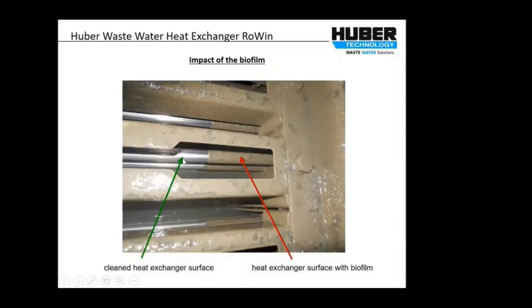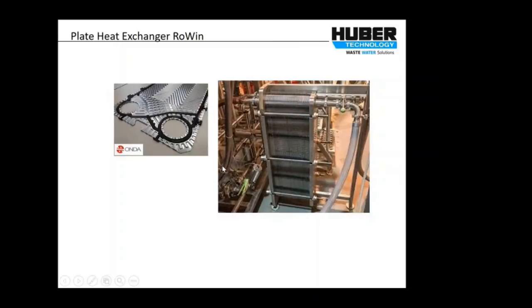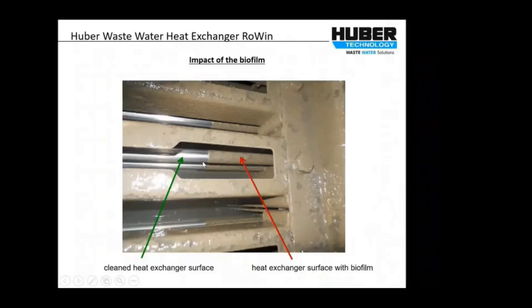We recommend a service every 10 years, and that's one of the key benefits of this unit. It is, to all intents and purposes, nominally a fit and forget. You only need to service these once every 10 years, and it's not a difficult service to undertake. The difference with a tubular heat exchanger, as you can see there, is they're fairly easy to clean, and there's a lot of space around here for the sediment to fall out, and additionally there's a lot of space for the biofilm to grow, and it's very simple to keep clean.